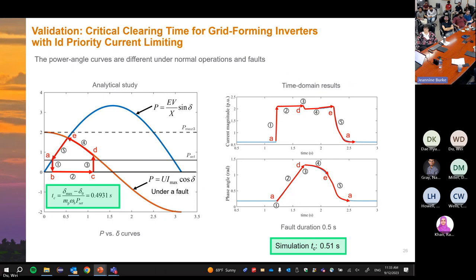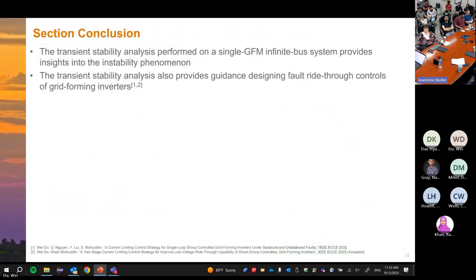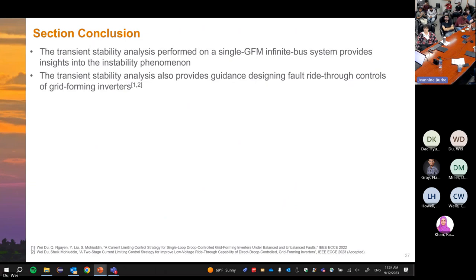The transient stability analysis of a single grid-forming inverter connected to an infinite bus provides insight into this instability phenomenon and helps in designing advanced fault ride-through controls. Unlike synchronous machines, whose critical clearing time is fixed by machine physics, inverters can flexibly change their controllers to avoid the critical clearing time. Understanding this phenomenon enables better controller design to ride through faults.